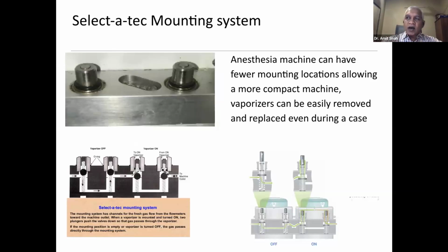Earlier, on the back bar, we were putting multiple vaporizers. But after we have ether, halothane, and then we add isoflurane and then sevoflurane, there is not enough space. So a system was added, called the Selectatec mounting system, which has fewer mounting locations, and the vaporizers were designed in a way that you can remove one vaporizer and put another even during the procedure or surgery. When you put it on this particular point, it presses this particular area, and when it presses this area, it opens up and the gas passes through the vaporizer and comes back through here. So this is how a Selectatec system works.